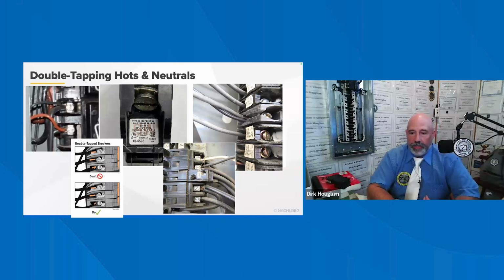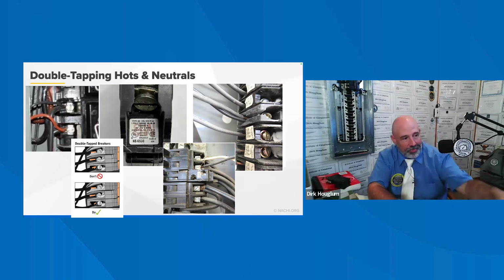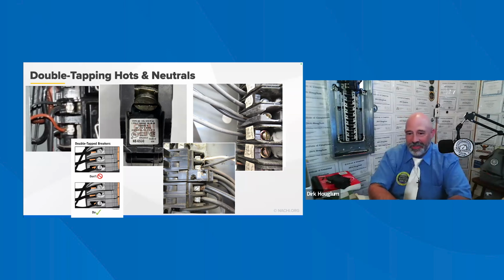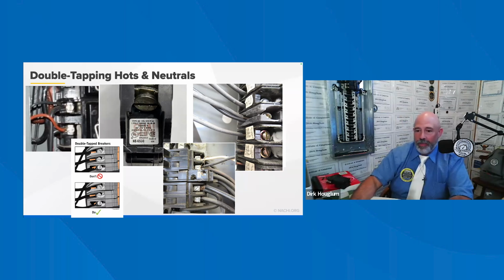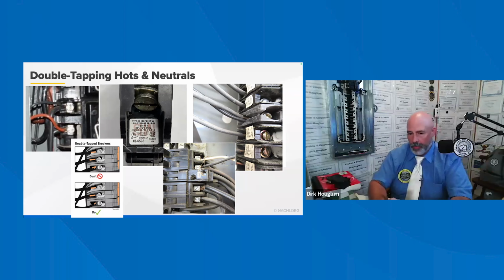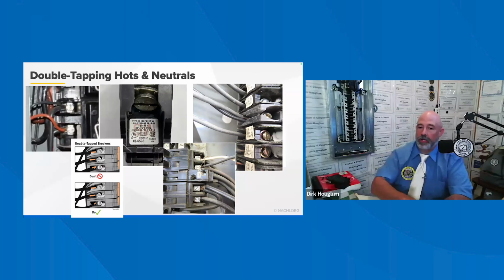The top middle inspection image shows Square D, and those are the ones that have the two wires, I believe. I can't read it, tell you the truth. Oh, yeah, I can. I got to go over on this side. Like I said, I got three screens here. So some breakers do accept those two. Double lugging or double tapping was never really permitted, but it was accepted for many years. And then all of a sudden people realized that it wasn't a good thing to do. When I was an electrician, we actually did it quite a bit. So now I know better, and now I call it out.